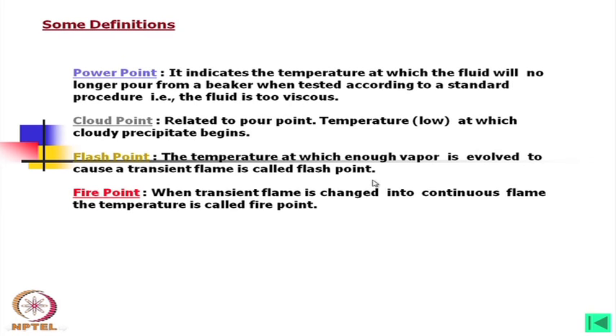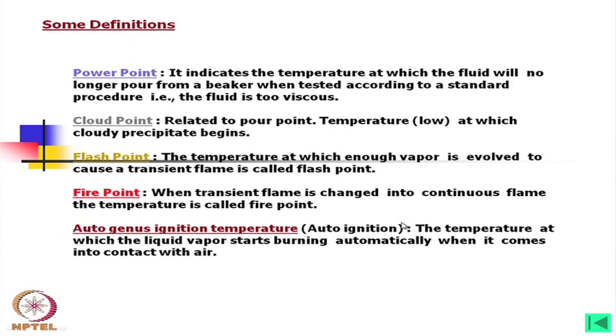Next to that, if you apply more heat, you will reach the fire point — when the transient flame is changed into a continuous flame, that temperature is called the fire point. At the fire point the flame is on the oil's top surface, but still the whole oil has not caught fire.